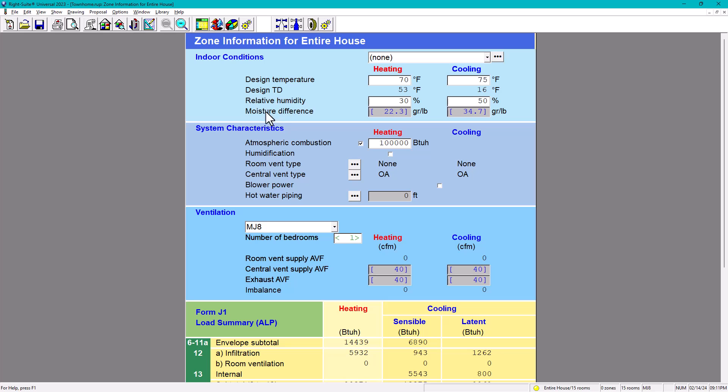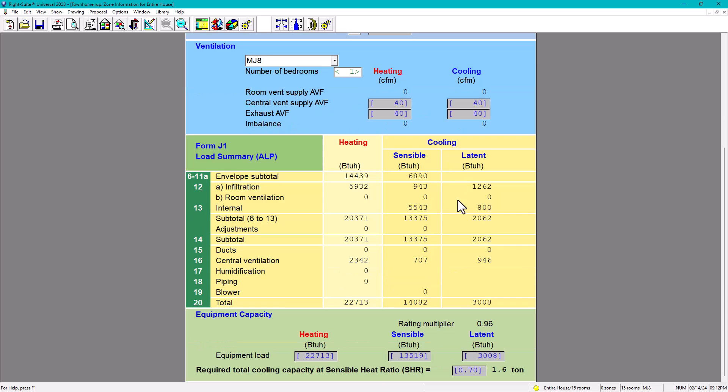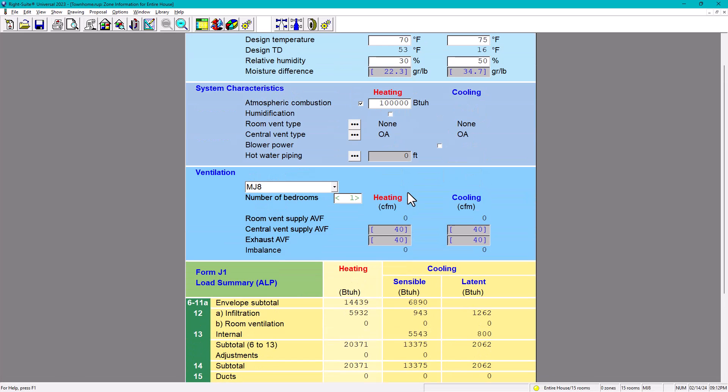Now, another system characteristic in here, it says blower power. So that is a big difference. This really makes a difference. So if you want to check in here and you want to be what they call conservative, check it, otherwise uncheck it. So what does this refer? Usually when you have equipment and it has a fan, it releases power and that power has heat - produces heat and that heat is sensible. In other words, it's going to add to your load, actually a lot. So what we're going to do in here is I'm going to check it later and we're going to see how much this tonnage increases. Next, what is hot water piping? In this case, we don't have hydronic system. It's air only.